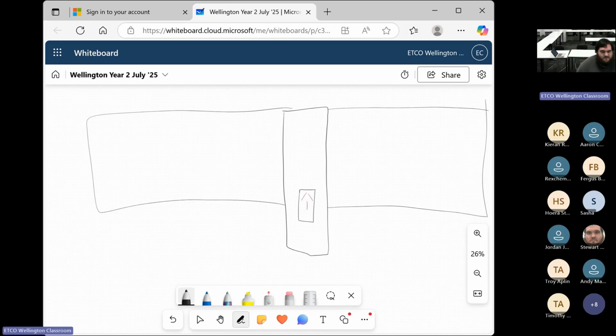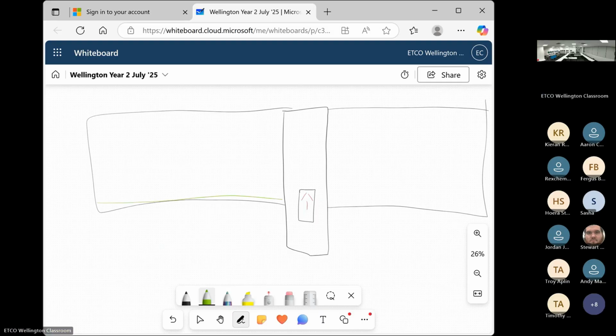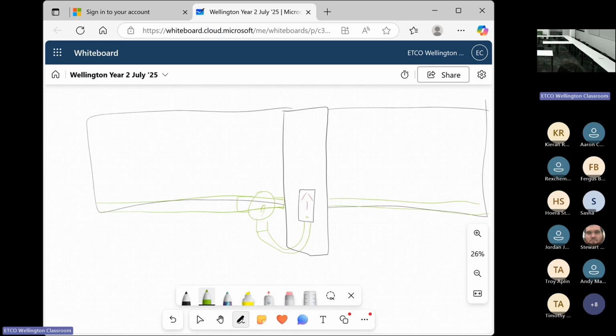Okay, one of the best things we can do for this is if we run our conduit, I'm going to use some green. So we run our conduit here. It goes behind the post and carries on. The best solution is we put a junction box here with a bottom entry, and we bring our flexible conduit down and up. The reason we do this is if moisture somehow manages to make its way into the junction box or into the power point, at least there is a chance that the blue water will gather here in the bottom of the conduit first. So we're lessening the possible dangerous side effects of moisture getting in, and at least making it so that the power point's going to last a while.